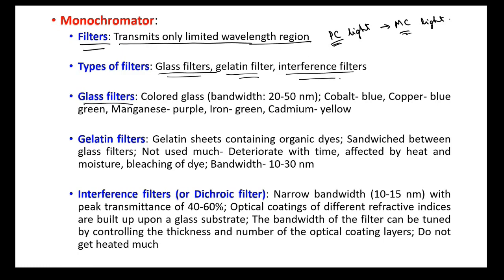Glass filters are easy to prepare. When preparing glass, metal ions with their own color are added, imparting color to the glass. These colored glasses have a bandwidth of 20 to 50 nanometers. For example, cobalt gives a blue color glass, copper gives blue-green, manganese gives purple, iron gives green, and cadmium gives yellow color glass.